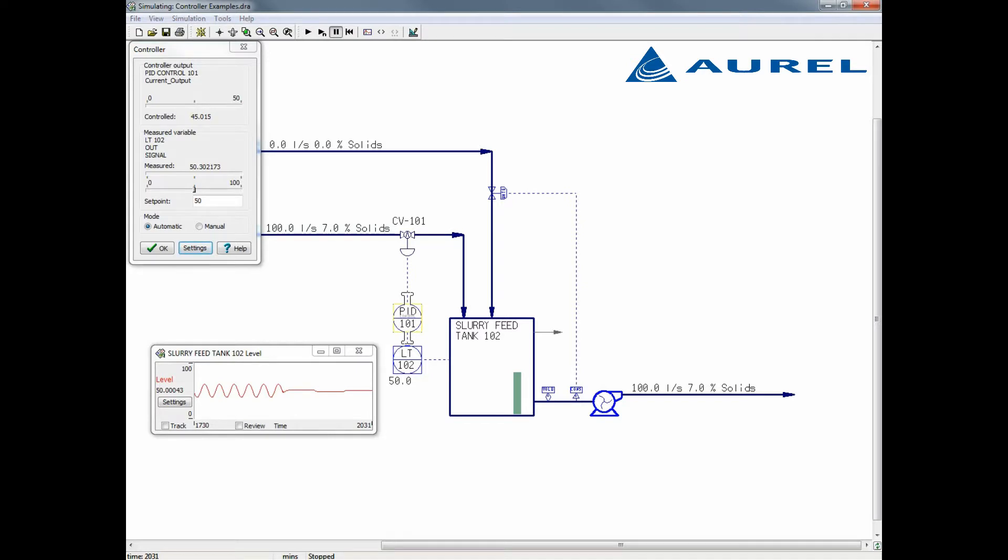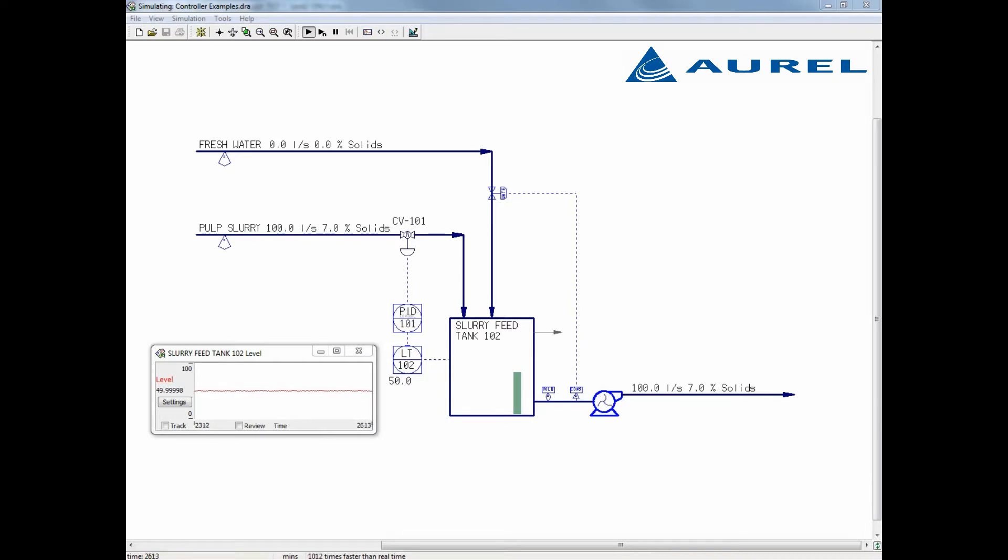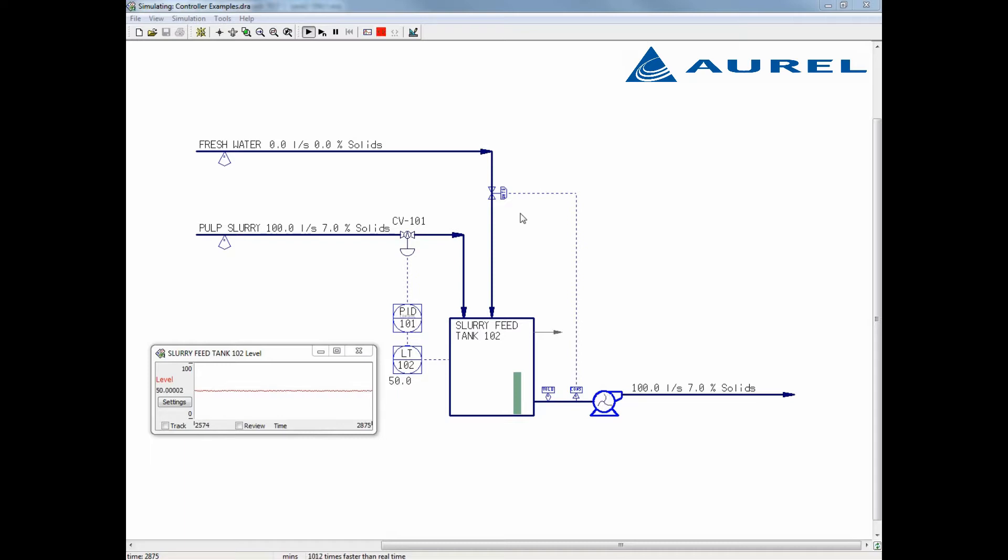As we run the simulation now, we see the tank level is much more stable. We also have a fresh water stream being fed into our tank, in order to achieve a consistency leaving the tank by diluting the pulp slurry. I will set up this flow with a shortcut controller to highlight some of the differences between this and the more formally drawn PID controller we set up previously. A shortcut controller will combine multiple elements into a single controller. For this example, our shortcut controller for fresh water flow incorporates the pump, valve, and controller all into one.